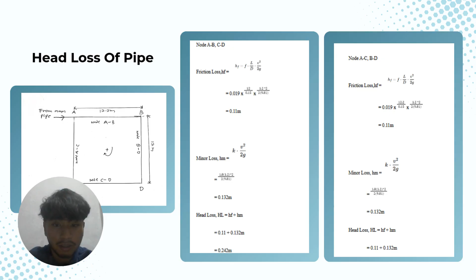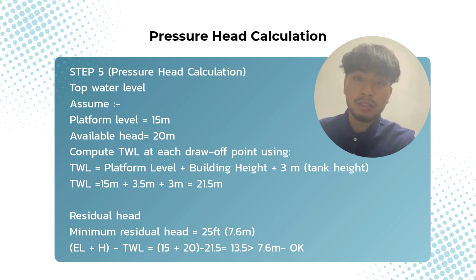For the pressure head calculation, we need to know the top water level, so we calculate it. We assume platform level 15 meters and available head 20 meters. The top water level is the platform level plus the building height plus 3 meters, giving a top water level of 21.5 meters. For residual head, the minimum residual head is 7.6 meters. The formula is platform level plus available head minus top water level. So 15 plus 20 minus 21.5 gives 13.5, which is over 7.6 meters. So for this project, it is okay.